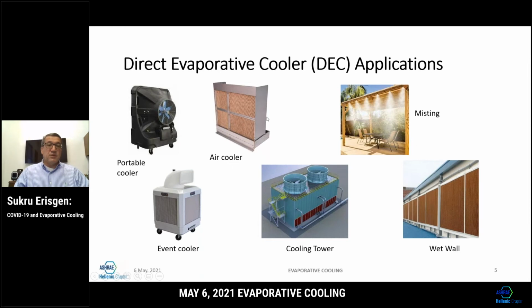Air coolers typically go into air handling units. These can be made with stainless steel housings and a number of stages. You can see two-stage configurations, stage 1 and 2, at 33% and 66% to control capacity, but it can actually be three-stage: 33%, 66%, and 100% range. So this type of equipment can give us a very wide range of cooling capacities.